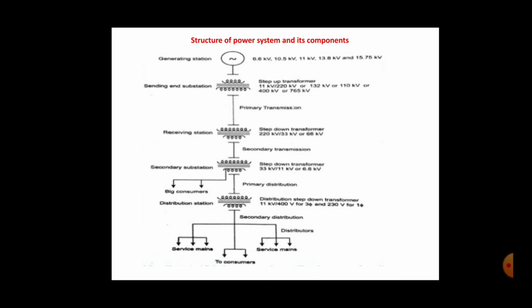When the power reaches the distribution transformer located near the consumer area, the electrical power is again stepped down from 11 kV to 400 volts for 3-phase 4-wire and 230 volts for single phase. Then the electrical power is provided to the customer end. This is the total structure of the power system network. You can see generating station, primary transmission, secondary transmission, primary distribution, secondary distribution and different consumers.